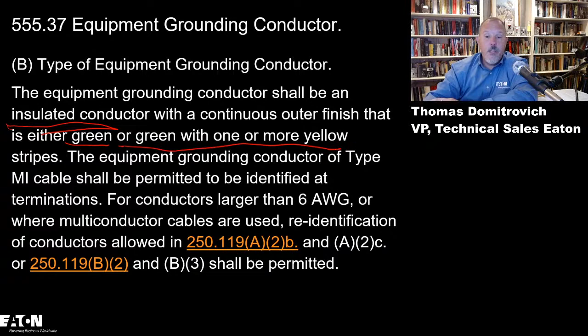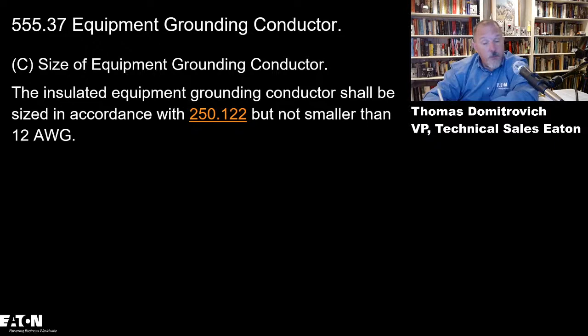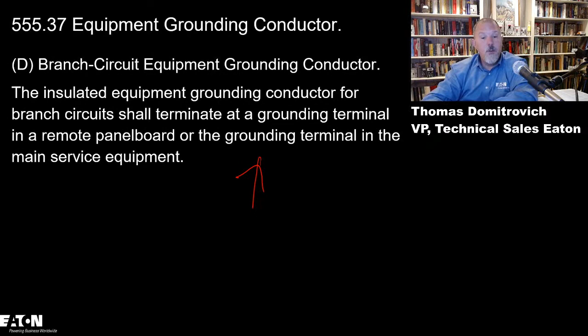So the equipment grounding conductors are going to be insulated in this area, and it shall be sized in accordance with 250.122, which is a good thing. So it's pointing us back to 250.122. Insulated equipment grounding conductors for branch circuits shall terminate at a grounding terminal in a remote panel board or the grounding terminal in the main service equipment. Talk about the feeders. Feeders supplying a remote panel board, insulated equipment grounding conductors shall extend from the...